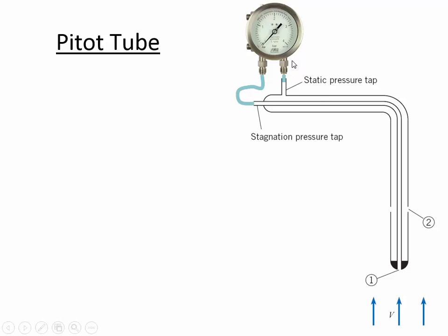Because if we go through the static pressure tap, it's kind of like a hollow tube that's encasing this center stagnation tube. It's kind of an ingenious setup that allows us to have whatever the surrounding atmospheric static pressure conditions are everywhere on the outside jacket of that inner tube that is carrying the stagnation pressure. And so the pressure is high in the center, and on the outside the pressure is less high. Everybody understand the maze there?